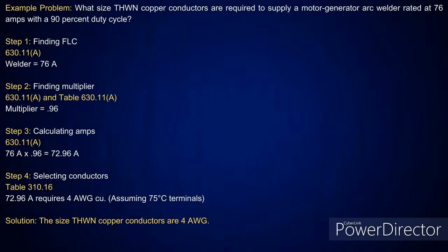About the current carrying conductors and how to do the calculation for adjustment and correction factor, or a combination of the two. Absolutely, that's a good catch, Danny, because that's something everyone has to remember: this is not just a be-all and end-all. You have to consider all these different temperature adjustments, everything. Like you can't just assume anything in the NEC.